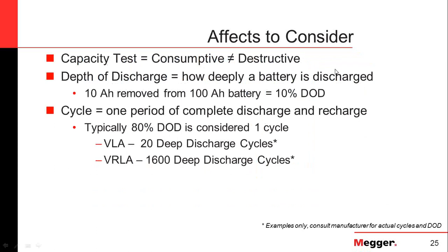A common question: is capacity testing destructive? No, it's not destructive — it doesn't destroy the batteries. However, it is consumptive; it does consume some of the battery life. Two related terms: depth of discharge equals how deeply a battery is discharged — think of it as the opposite of a charged state. If I'm at 100% charged, that's 0% discharged. If I consume 10 amp hours out of a 100 amp hour battery, I'm at 10% depth of discharge or 90% charged state.